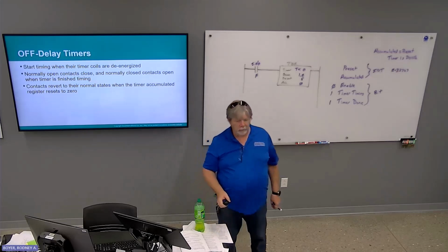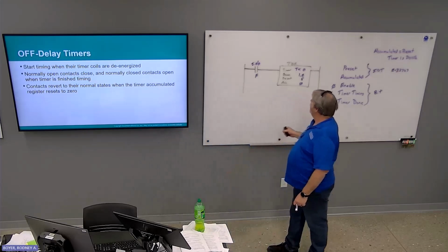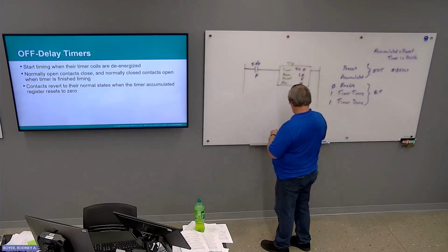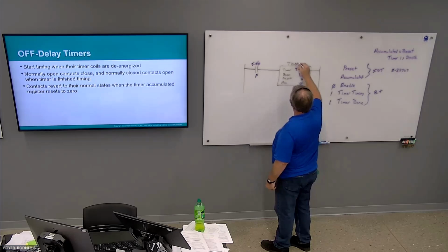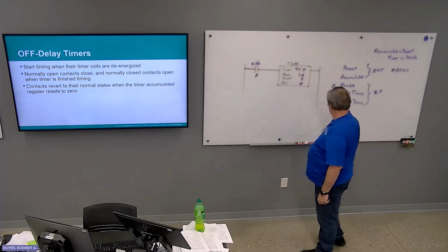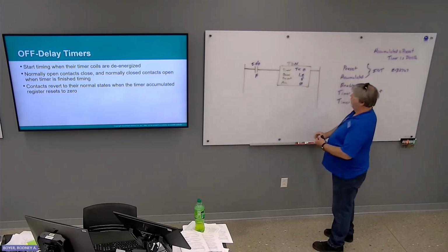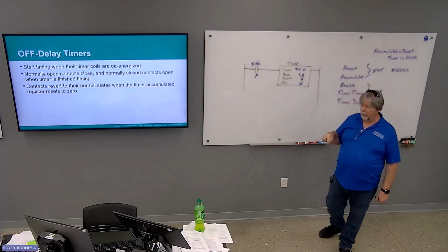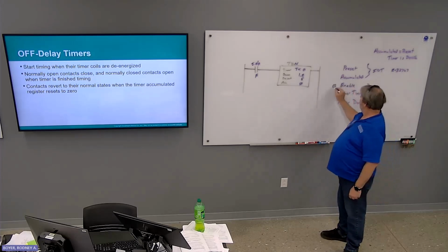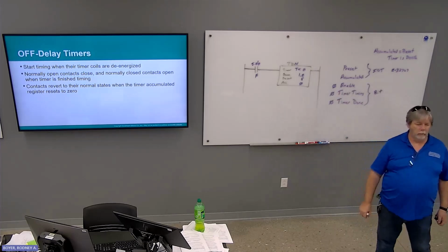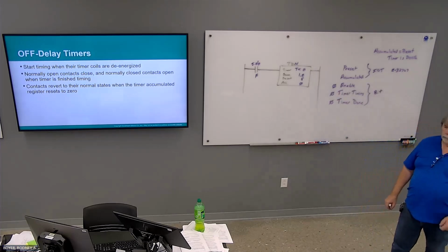With an on delay timer, let's change this to an on delay here real quick. As long as my conditional logic is false, enable, timer timing, and done are all cleared to 0.